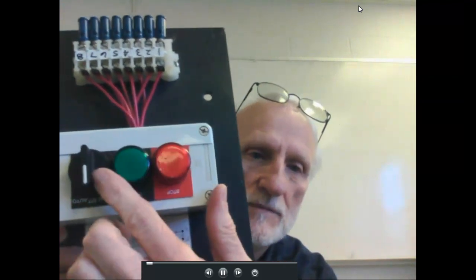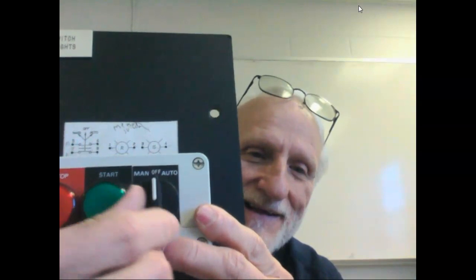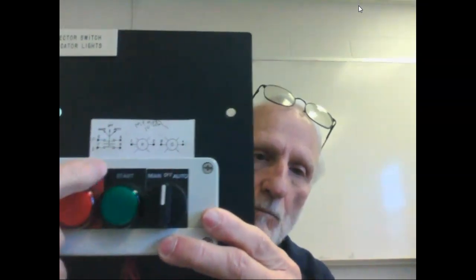We don't use a lot of toggle switches in motor controls because they're very easy to accidentally actuate. Here's the selector switch — it's a three-position switch. It's got one labeled auto and one labeled off. When I switch it off, both contacts would be open. If I go over and switch it to manual, these are just labels.